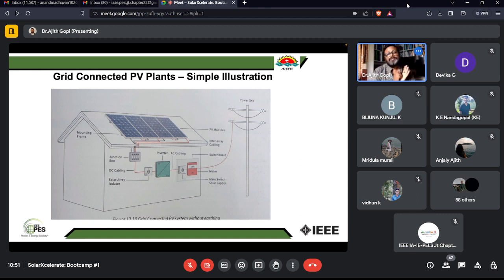I'll repeat. You have DC cables coming from the strings of the solar panel arranged, coming to the DC junction box. This DC junction box will have a DC isolator, and it will have a switch fuse unit, which is optional. Generally it will have an SFU, and definitely there will be a DC SPD, the surge protection device. Then it goes to the inverter.